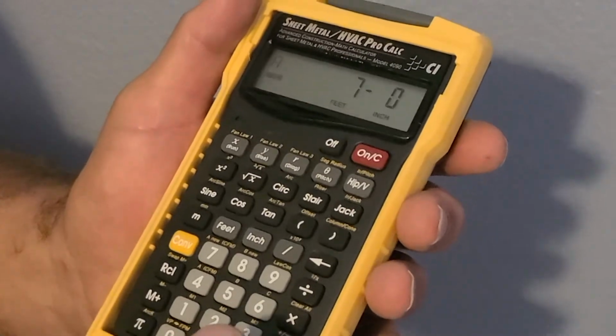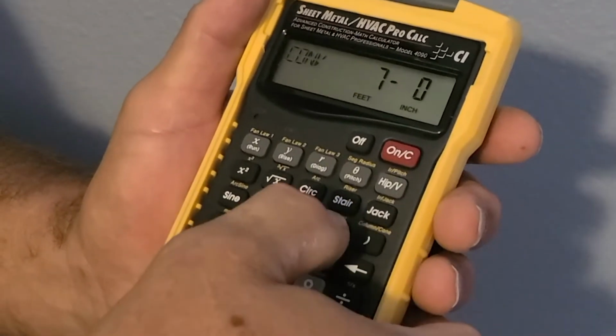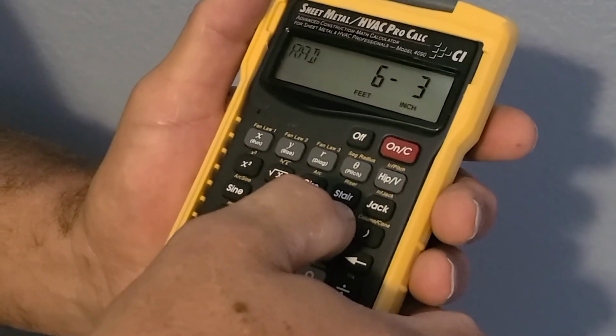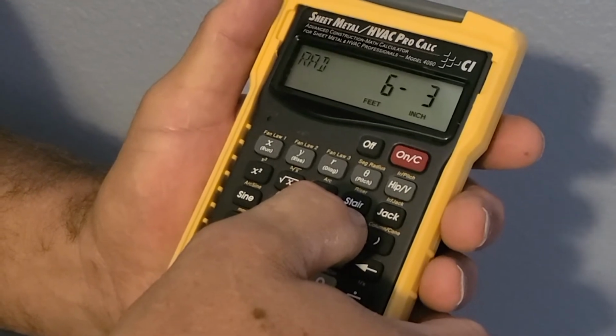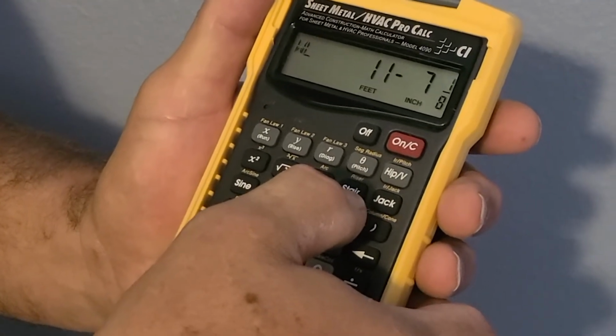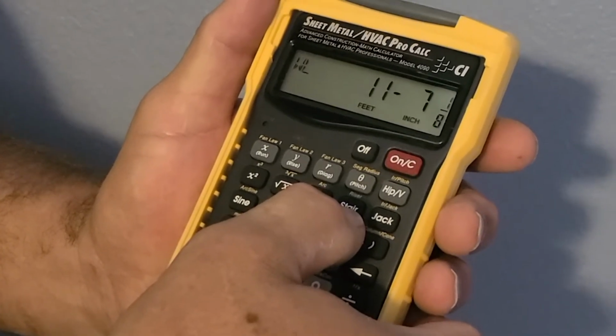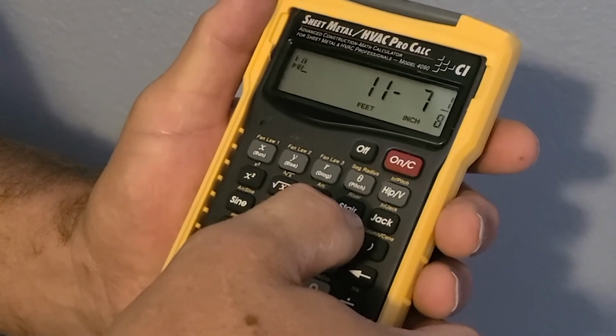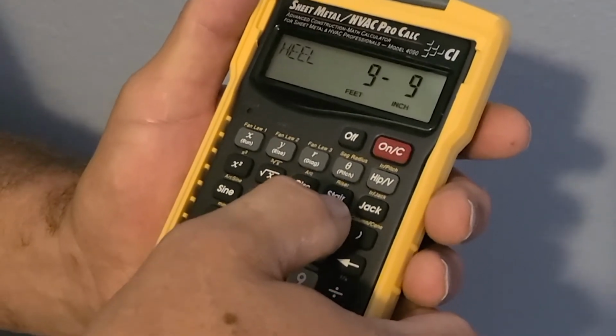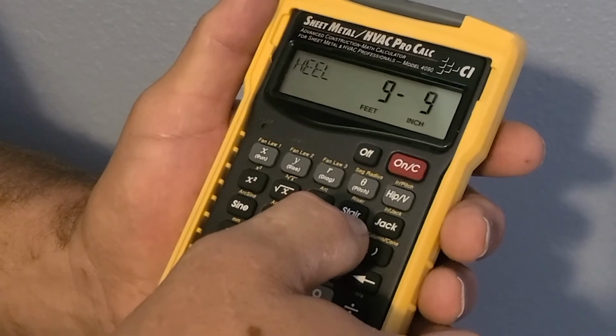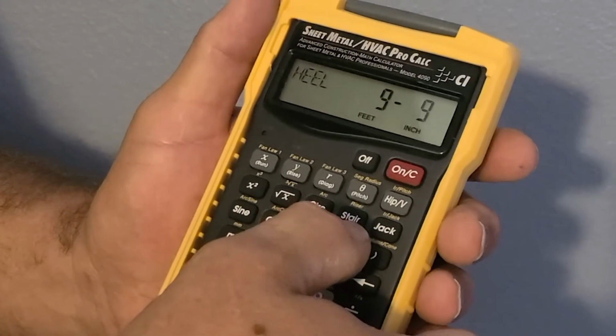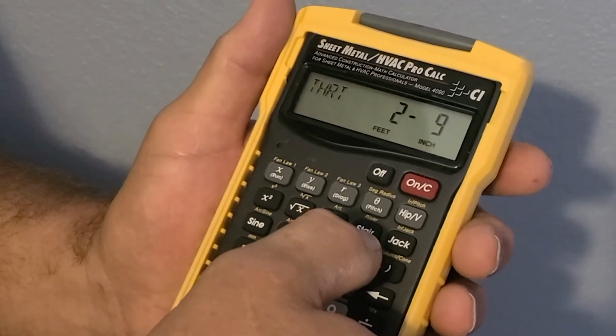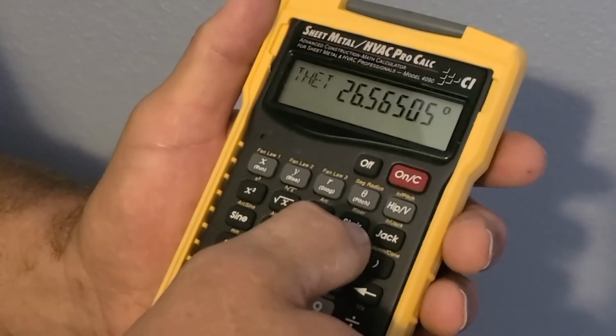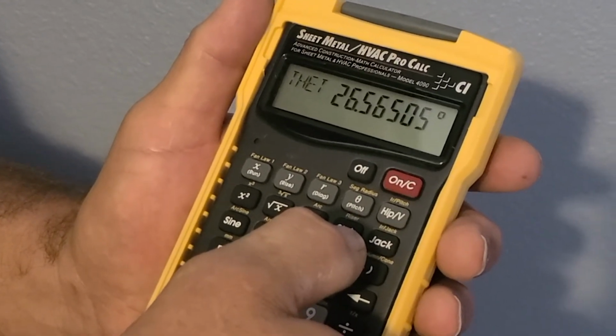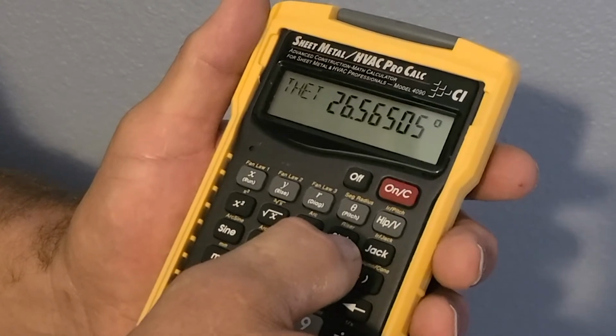The calculator does the rest. Press convert parentheses. The first answer is the radius of 6 feet 3 inch. The second push of the parentheses gives you the wrapper length, or WL, which is 11 feet 7 and 1/8 inch. The third push gives you the heel measurement of 9 feet 9 inch. The fourth push gives the throat measurement of 2 feet 9 inch. And the fifth push gives you the theta, which is 26.56505 degrees.